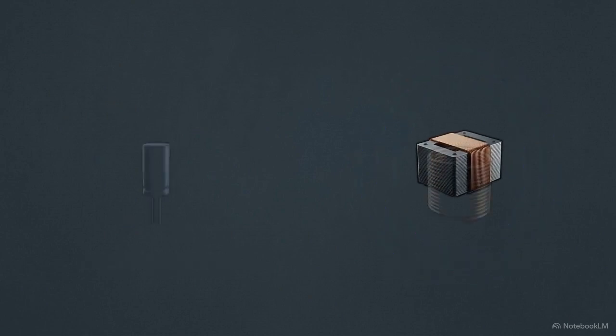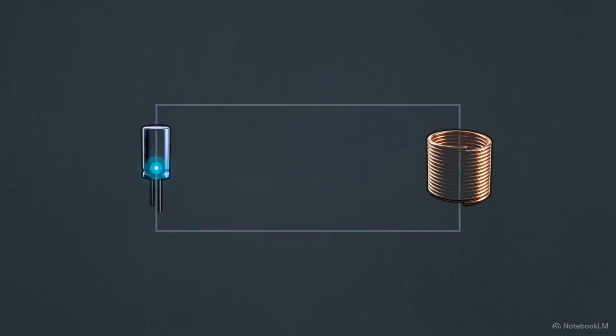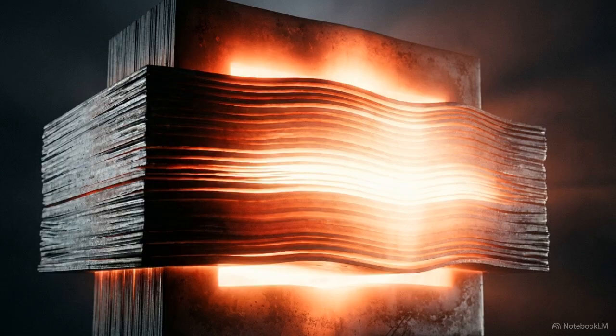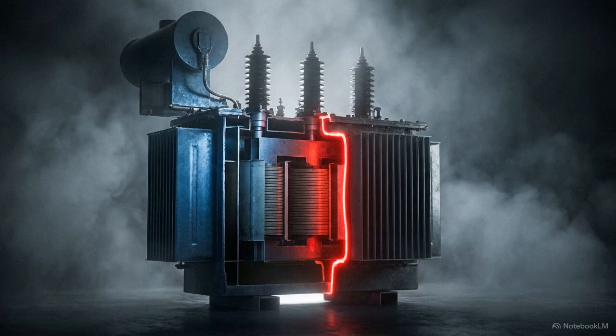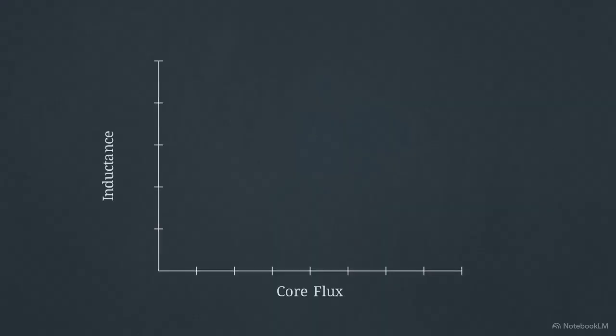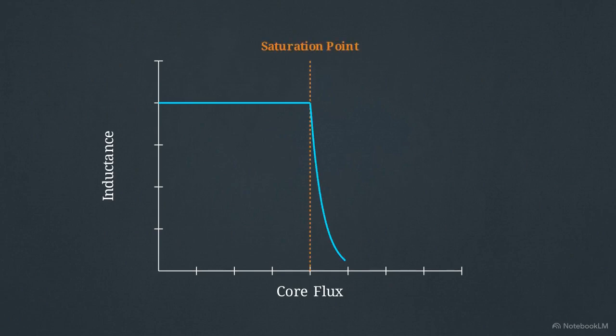In a normal state of electrical resonance, these two components form a balanced partnership. Energy trades back and forth between the cable's capacitance and the transformer's inductance in a smooth, predictable rhythm. The problem starts when the iron core of the transformer is pushed past its magnetic capacity. The core hits a hard physical limit. In engineering, we say the core has reached nonlinear saturation. Once that saturation point is reached, the physics of the transformer shift. Its ability to oppose changes in current, its inductance, plummets.